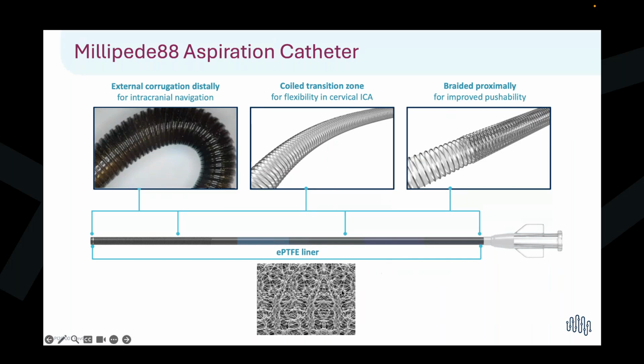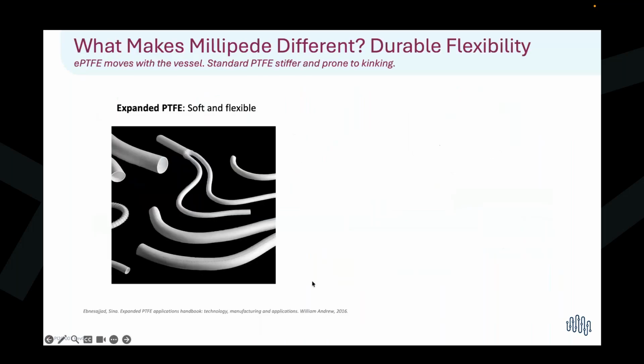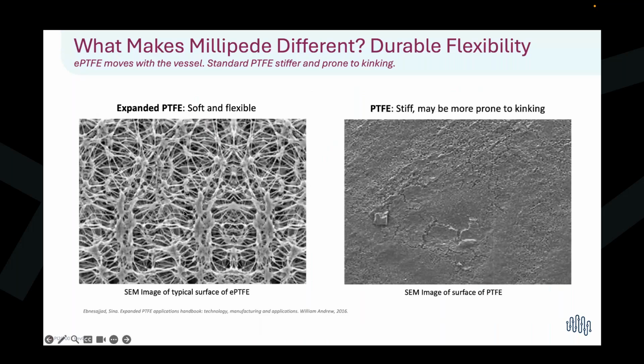EPTFE liner, which is a little bit different than the typical PTFE liners that we're using. And so when we look at scanning electron microscopy of this, you can see that the EPTFE looks a little bit more like a sponge, and the PTFE looks a little bit more like a homogeneous surface, like a painted wall. And this translates to a tremendous difference in flexibility. So the EPTFE has much more flexibility and resilience. And so this acts much more like rubber, whereas the PTFE behaves a little bit more like cardboard. It's a little bit more stiff.